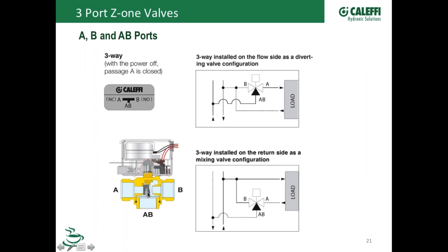Now, I know there's something else, Cody, you wanted to talk a little bit about, because this valve could be sent out, or could be installed, I should say, with a normally closed or a normally open actuator on it, and that would just change the position of the flap with the power off, right? Yeah, for sure. So like you notice in the graphic there, port A is the normally closed and port B is the normally open.